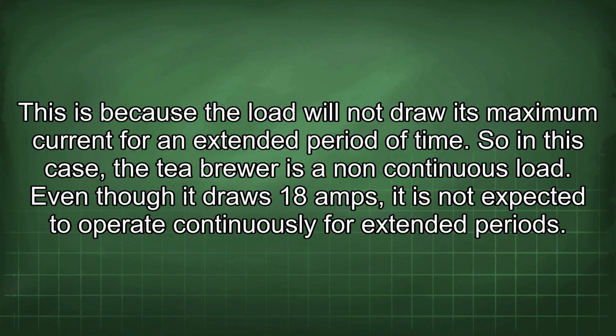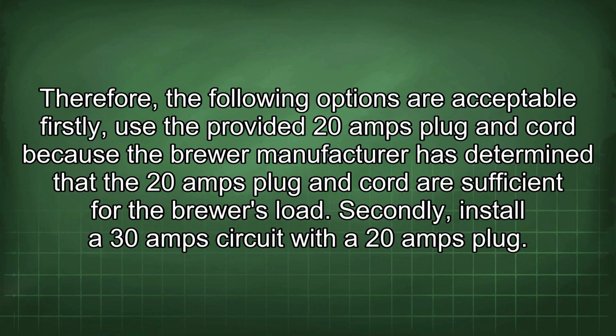So in this case, the tea brewer is a non-continuous load. Even though it draws 18 amps, it is not expected to operate continuously for extended periods. Therefore, the following options are acceptable. Firstly, use the provided 20 amps plug and cord because the brewer manufacturer has determined that the 20 amps plug and cord are sufficient for the brewer's load.